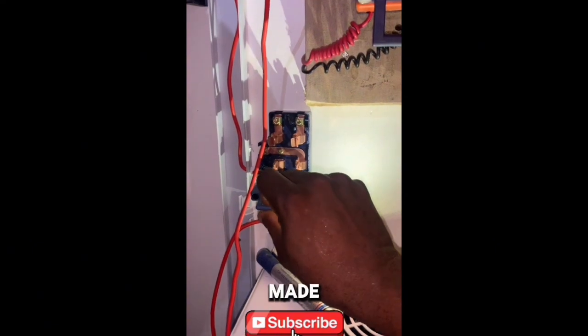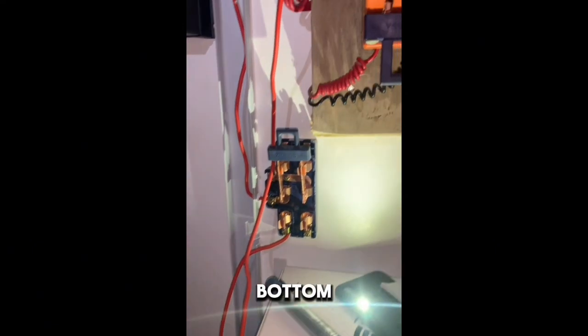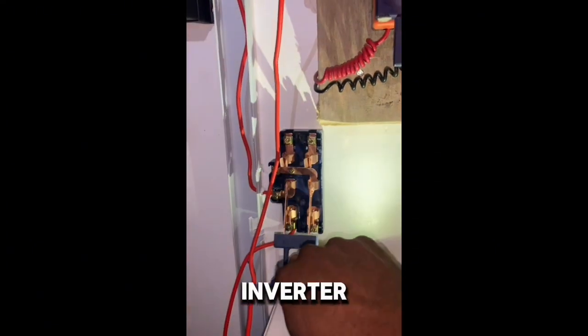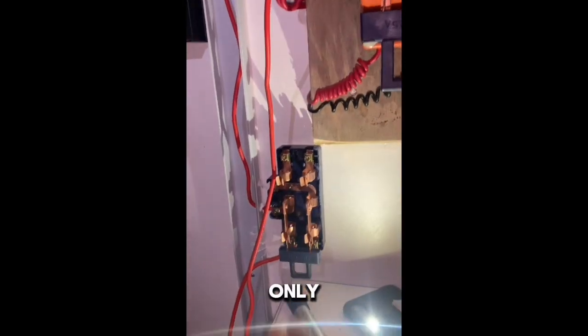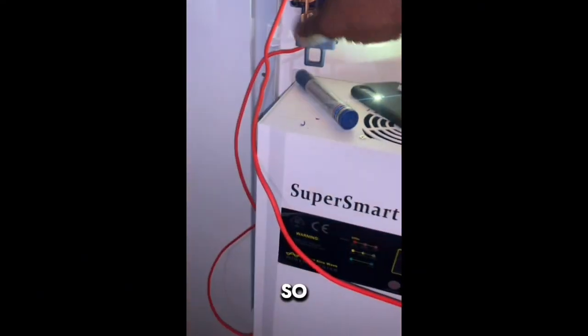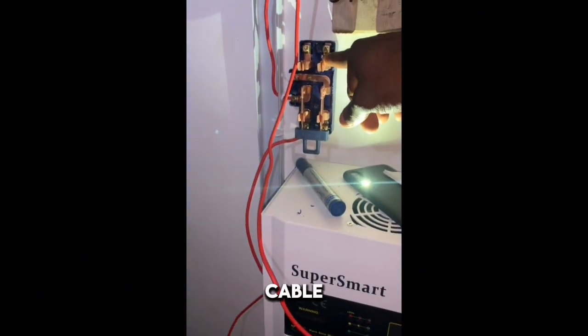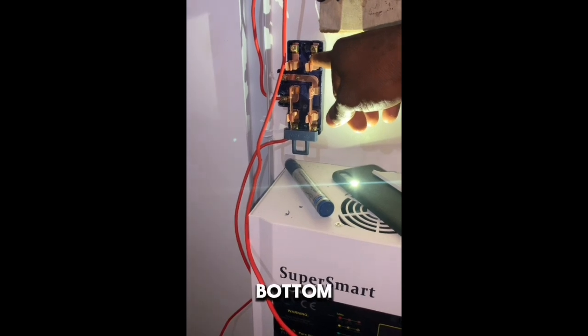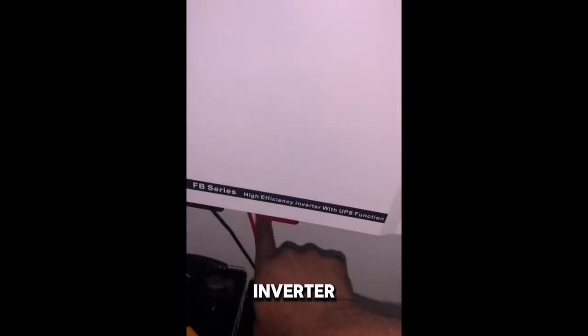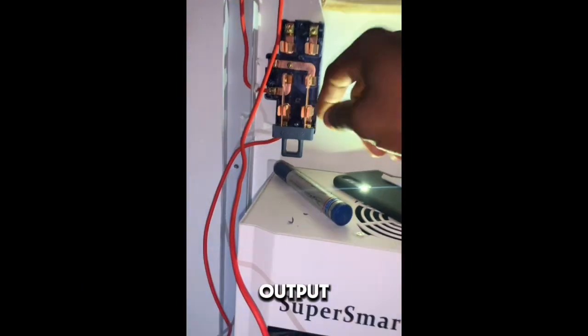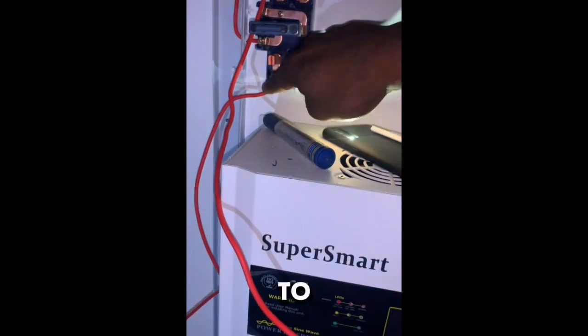But this very one, if it's there at the bottom, is going to be for the inverter, while the top is going to be for the bypass. The bypass is only used when there is a fault with the inverter. So the cable from the bottom side comes from the load output of the inverter. The output from the load output comes to this very changeover. So this is the other one that goes to the top.